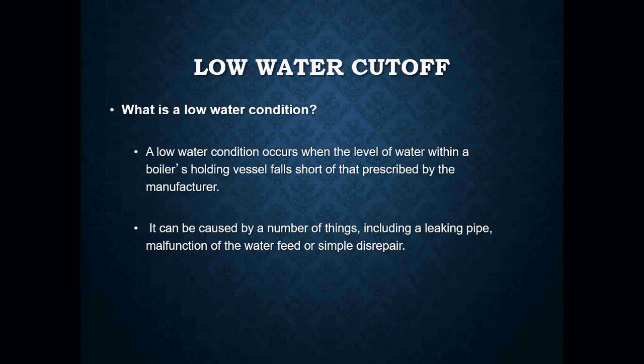A low water condition occurs when the level of water within a boiler's holding vessel falls short of that prescribed by the manufacturer. It can be caused by a number of things — you can have leaky pipes, which can be very visible, a malfunctioning water feed, or simple disrepair.